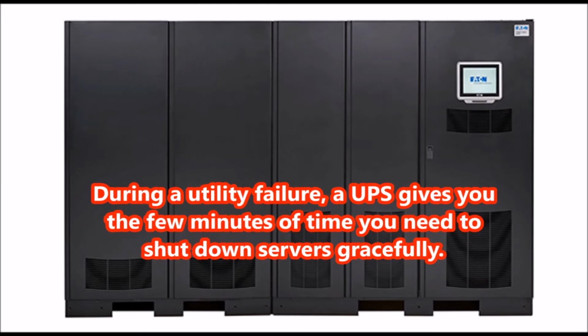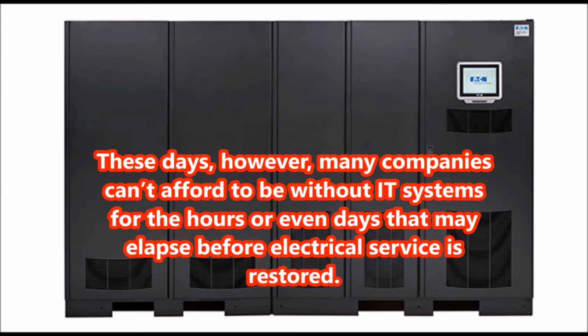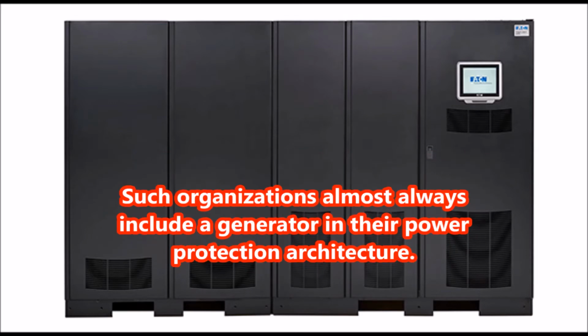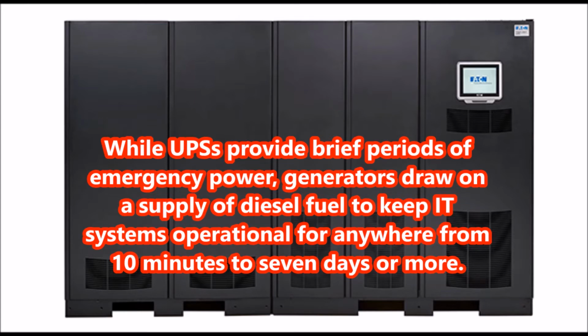Generator. During a utility failure, a UPS gives you the few minutes of time you need to shut down servers gracefully. These days, however, many companies can't afford to be without IT systems for the hours or even days that may elapse before electrical service is restored. Such organizations almost always include a generator in their power protection architecture. While UPSs provide brief periods of emergency power, generators draw on a supply of diesel fuel to keep IT systems operational for anywhere from 10 minutes to 7 days or more.